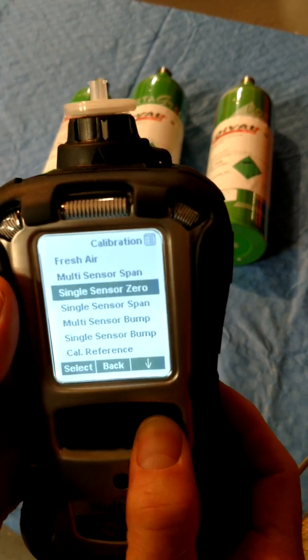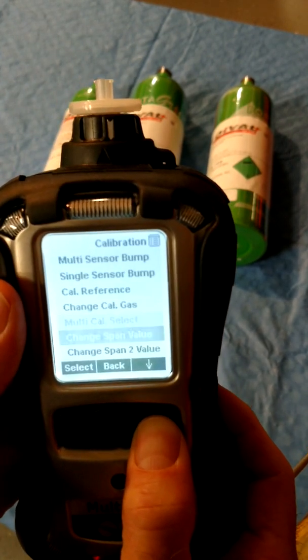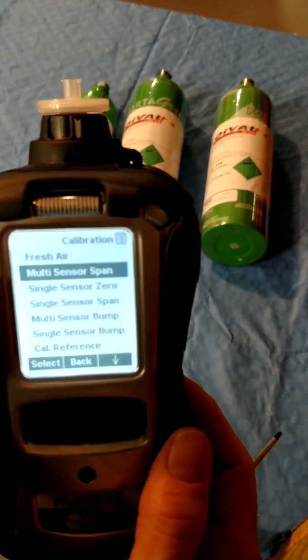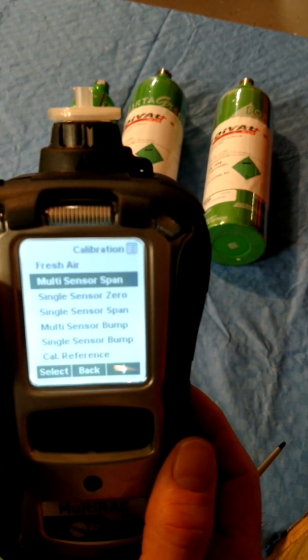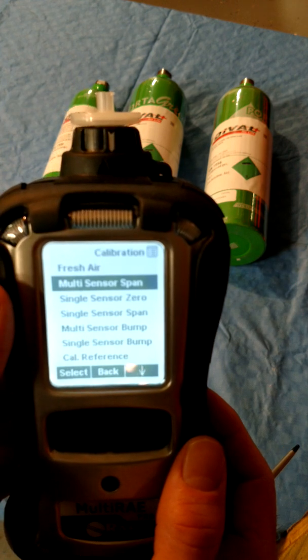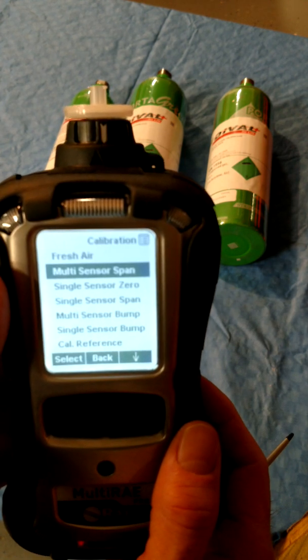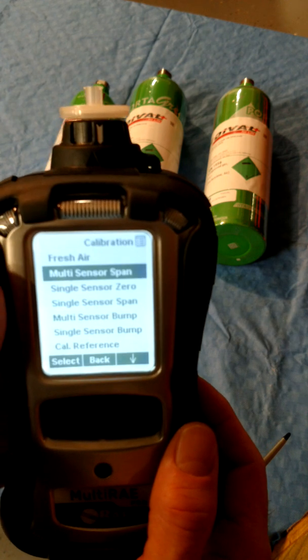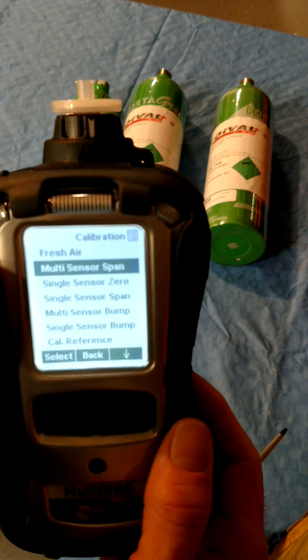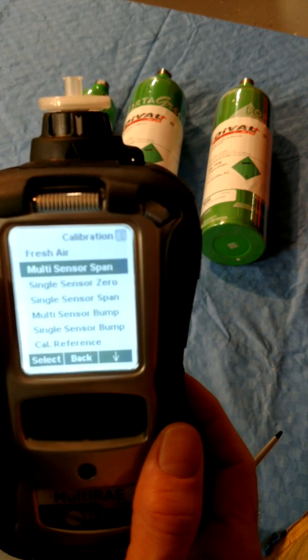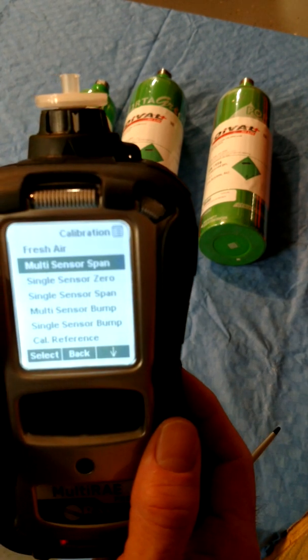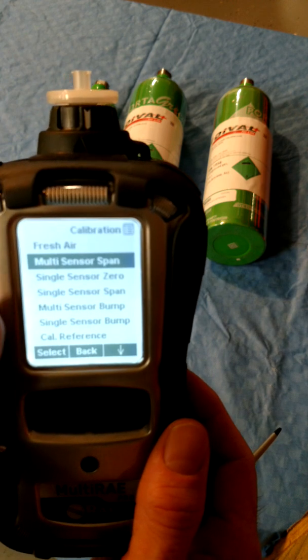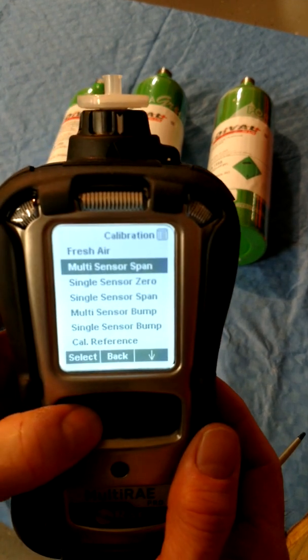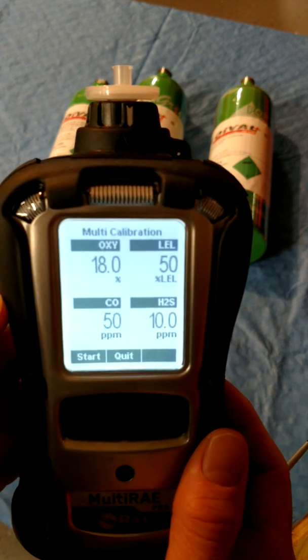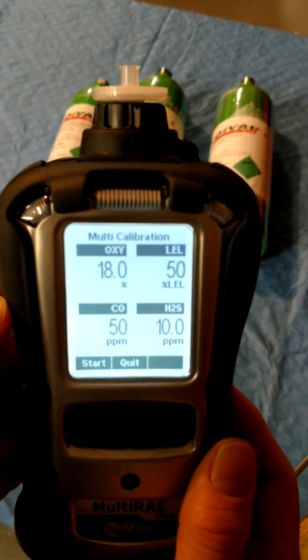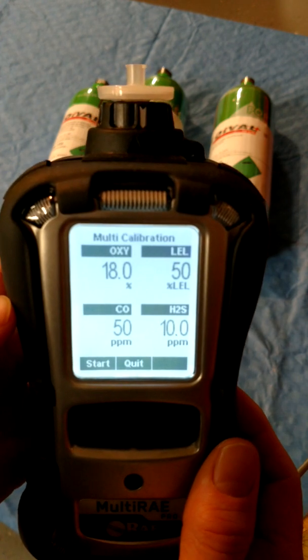Span cal is accessed via the multi-sensor span option on the screen. Our meters are configured to simultaneously calibrate all gas sensors with the exception of the VOC sensor. After they are calibrated, the meter will automatically prompt the VOC cal check. So I'll select multi-sensor span. You can see the 4 sensors that will be calibrated and their appropriate responses.